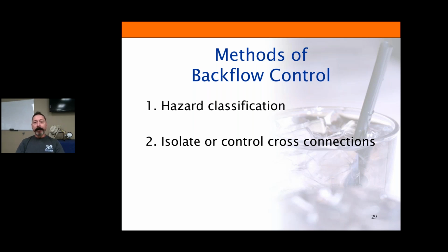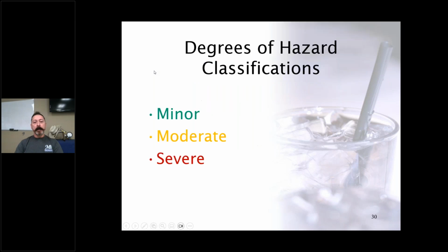So, methods of backflow control. All cross connections are assigned a hazard classification. And then there are typical means of isolating those connections by means of backflow preventers or an arrangement of piping. In the case of hazard classifications in Canada, the manuals and the standards divide these hazard classifications into three types: a minor hazard, a moderate hazard and a severe hazard.